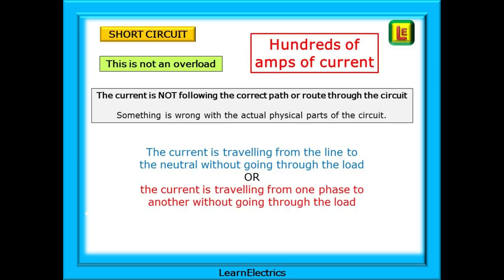So, a short circuit is completely different to an overload. Hundreds of amps of current will flow. The breaker will trip almost instantly. The current is not following the correct path or route through the circuit. Something is wrong with the actual physical parts of the circuit. Something is broken or damaged. Something has happened. The current is travelling from the line to the neutral without going through the load. Or, in a three-phase system, the current could be travelling from one phase to another without going through the load.